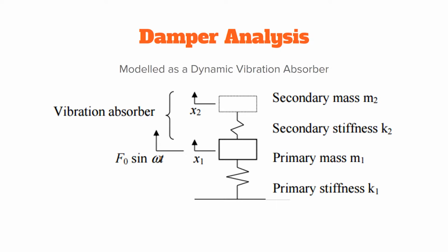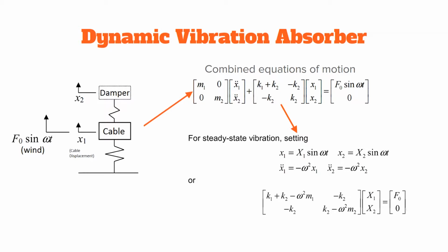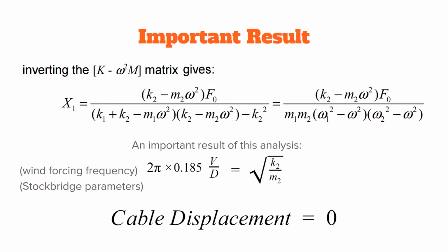The Stockbridge damper can be modeled analytically as a dynamic vibration absorber. Dynamic vibration absorbers are used for suppressing steady-state amplitudes at resonance. They consist of a secondary mass attached to the primary system mass by a secondary spring. For the free body diagram, the combined equations of motion can be constructed. During steady state, the vibration amplitudes for the cable and the Stockbridge damper will be in the form of a sine wave. Therefore, the acceleration of the displacements can be found and substituted into the equations of motion. By inverting the frequency equation matrix, an equation for solutions to the amplitude of the cable's vibration is acquired.